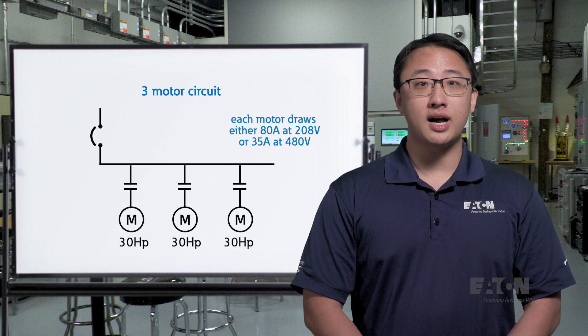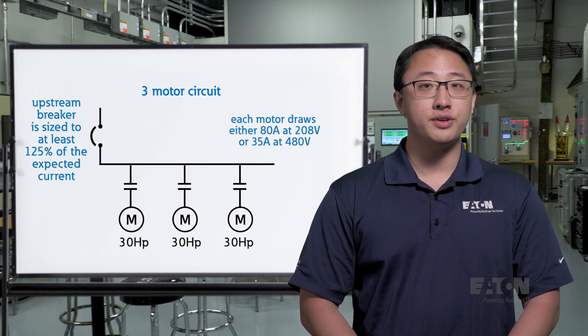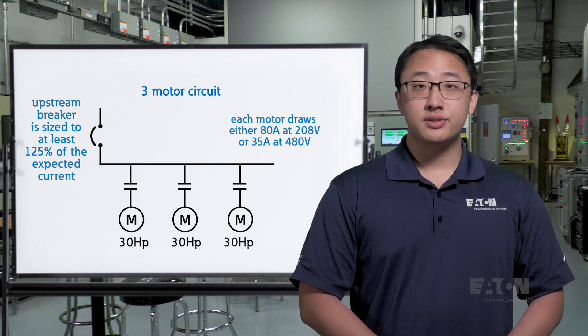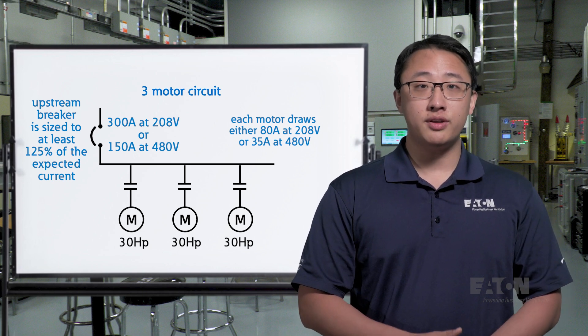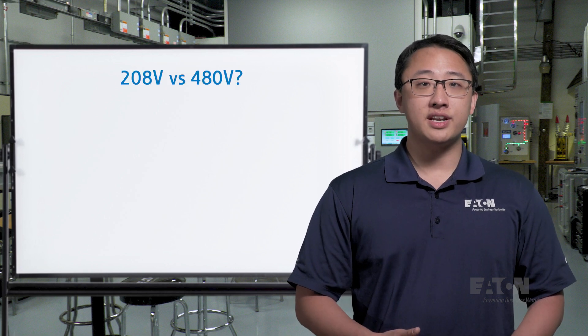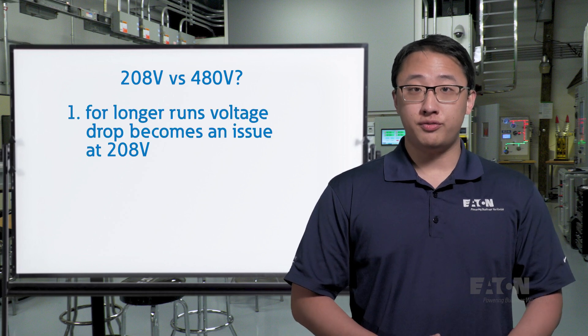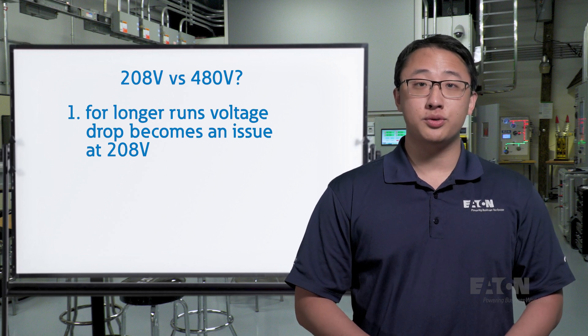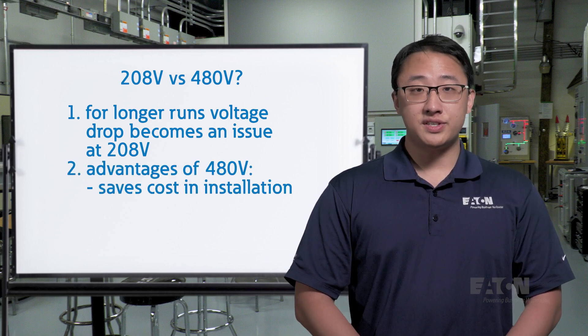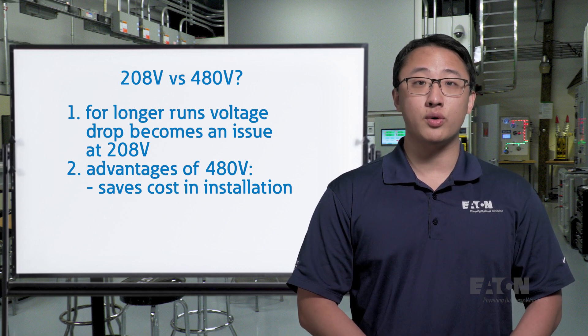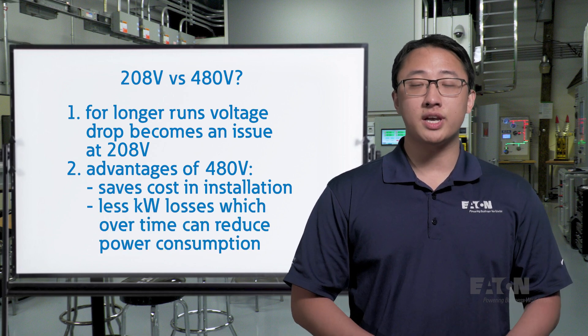Knowing this, we would first size the feeder cables to accommodate the current at the selected voltage for all three motors. In most applications, you would size the upstream breaker to at least 125% of the expected current. Running at 208 volts, the feeder would need to be sized at 300 amps capacity per phase, or if running at 480 volts, about 150 amps per phase. One factor in deciding between 208 or 480 volts is how far away your motors are from the transformer. With a 500-foot run, voltage drop becomes a concern at 208 volts since the higher current results in more losses. Using 480 volts saves money during installation because copper cabling for a 150-amp circuit costs significantly less than for a 300-amp circuit, and there are fewer kilowatt losses, which can reduce power consumption over time.